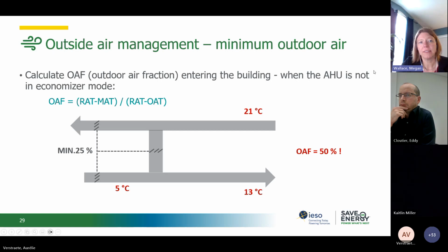We'll also calculate the outdoor air fraction entering the building when the air handling unit is not in economizer mode. To calculate the outdoor air fraction, you take the return air temperature minus the mixed air temperature. In this example, return air temperature is 21 and mixed air temperature is 13, divided by the return air temperature minus the outdoor air temperature. And we get an outdoor air fraction of greater than 50%.